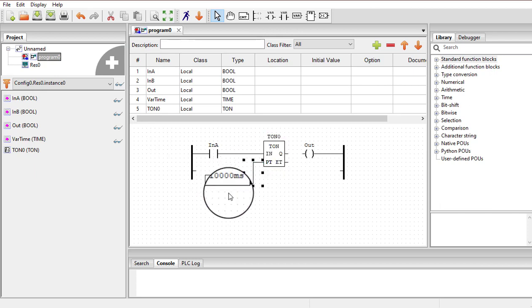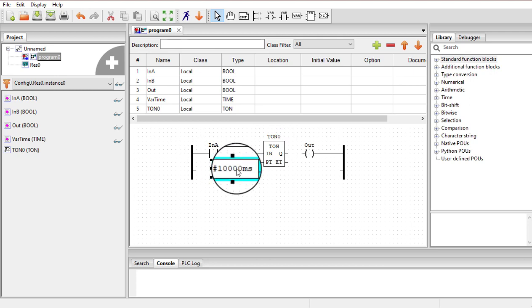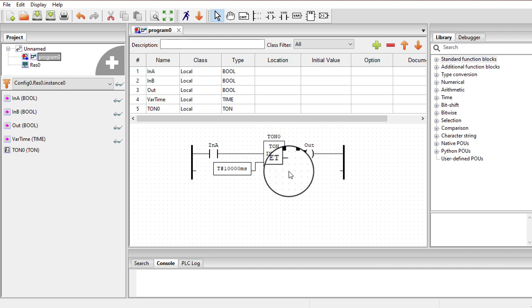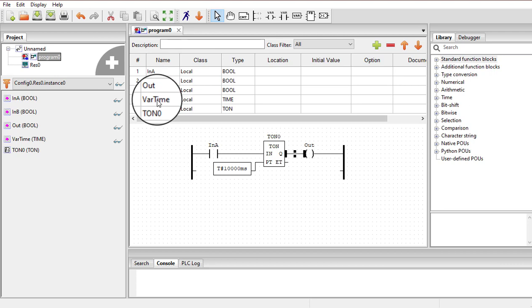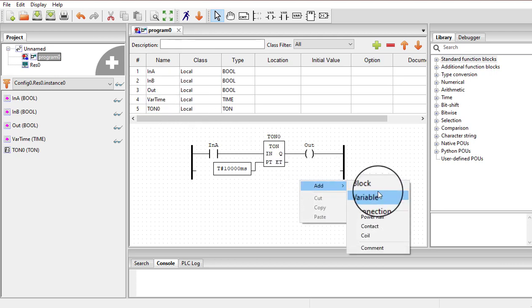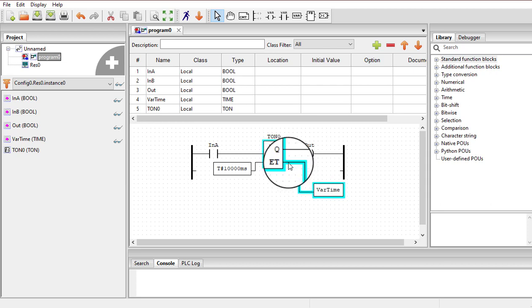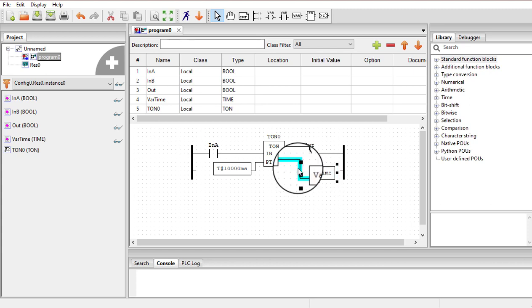When input A goes high, the timer will start timing and keep timing until 10 seconds are over. After 10 seconds, the Q terminal goes high. If we attach the output to the Q terminal, the output will turn on after 10 seconds. The ET terminal is the elapsed time — it shows how much time has elapsed at a particular moment. You can store this in a time variable, which is why we created variable time. You can omit the time variable altogether — the timer will still function well.